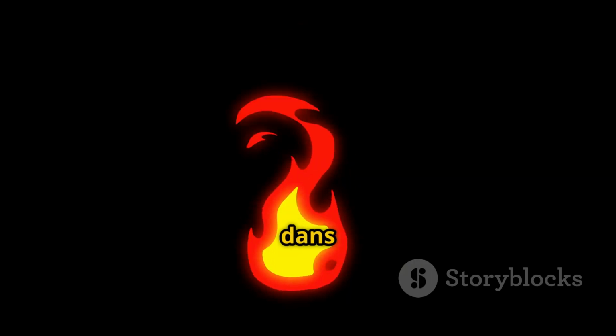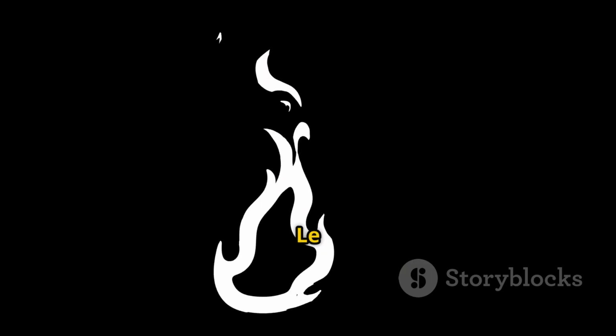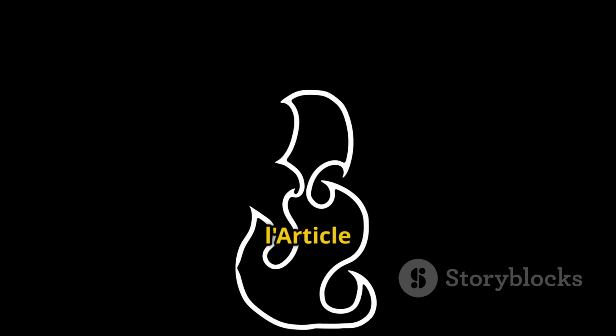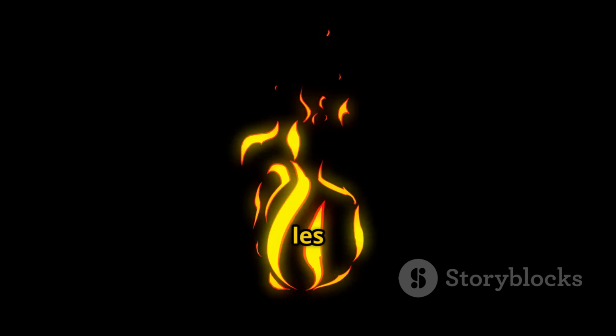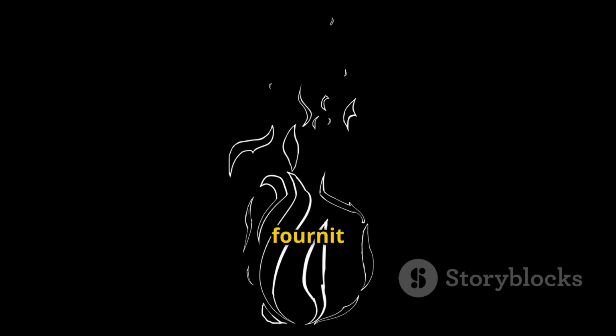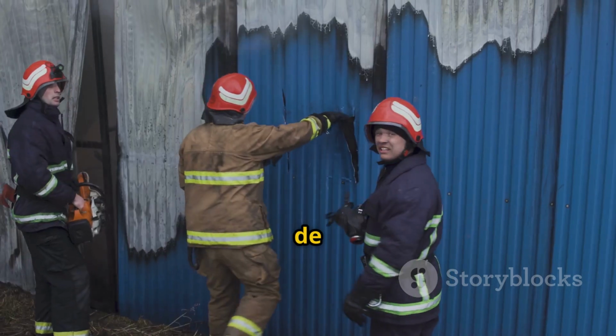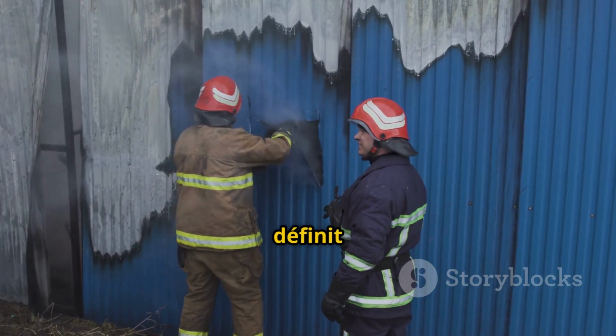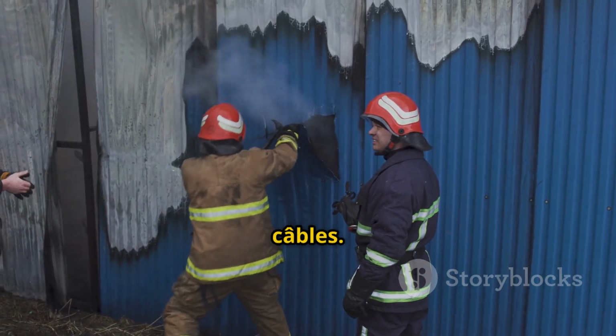Another significant safety benefit relates to the behavior of cables during a fire. In a traditional conduit installation, a fire that starts at one end of a pipe can propagate through the entire length of the conduit, using the cable insulation as fuel in an enclosed, chimney-like space. This can allow a fire to spread unseen through walls and floors to other parts of a building.